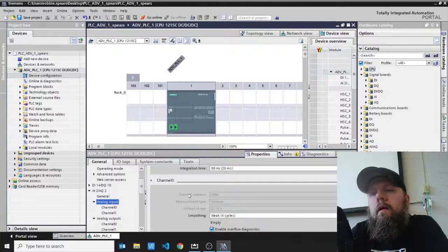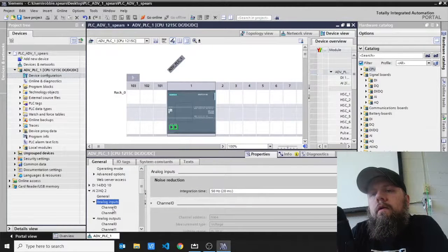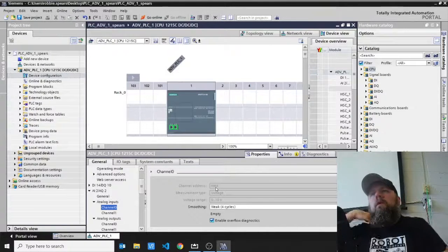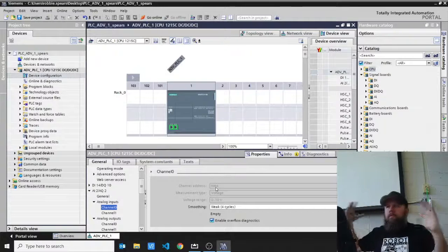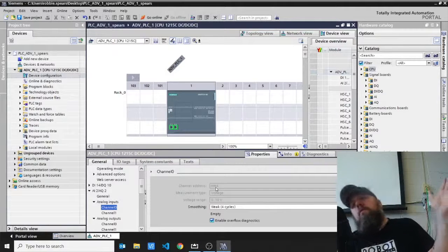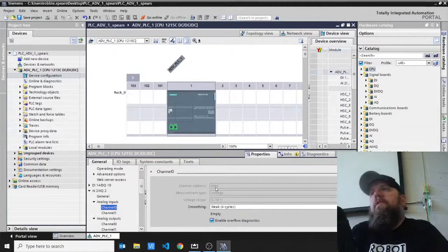Now click on channel 0. That's going to be your first channel, and it's hard coded as IW64. A W is a word, which is a pretty big chunk of memory, because we're going to have to store 0 through, let's say, 30-something thousand.